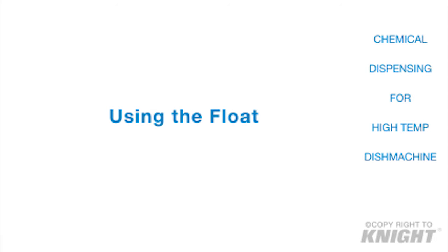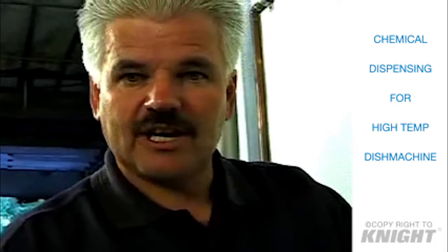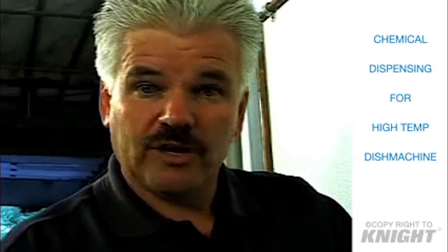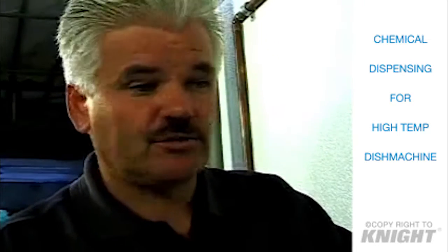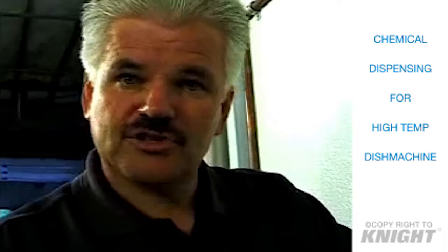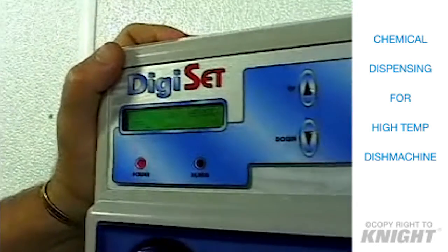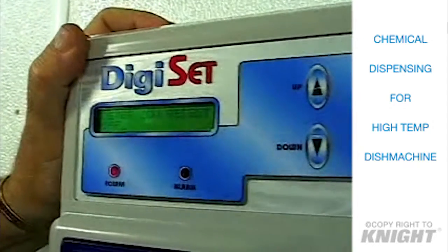The downside is that in probeless operation, you lose the option of being able to use an alarm, because with a probe in the tank, we can sense when there's a lack of alkalinity in the tank. If it stays like that for too long, the alarm is going to go off inside the control to let you know you're out of soap.